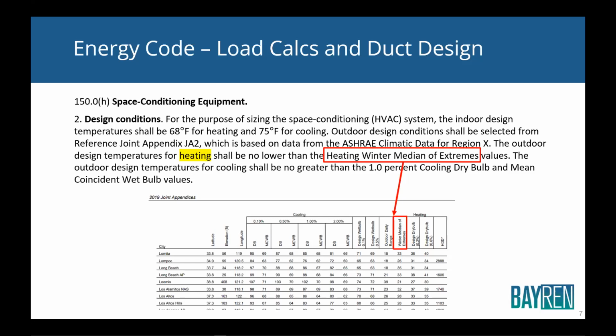All right. So one of the things that applies to everybody who's doing a load calc is picking your design temperatures. And our code actually specifies which design temperatures to use. It's a little different than manual J, but if you just follow manual J, it will tell you which design temperatures to use. So the heating design temperature is something called the winter median of extremes. And it's listed for each city, which will have all these design temperatures. And manual J will say, for heating, use this one, and for cooling, use this one.